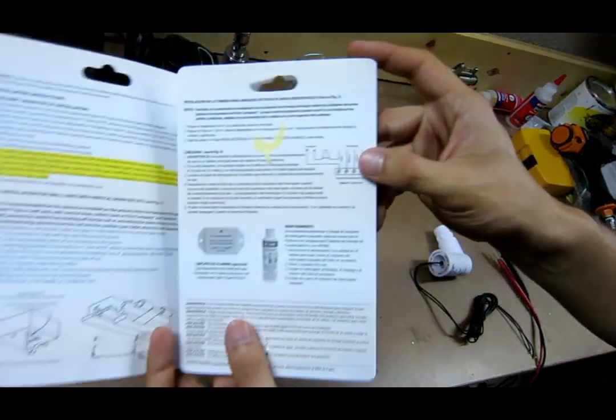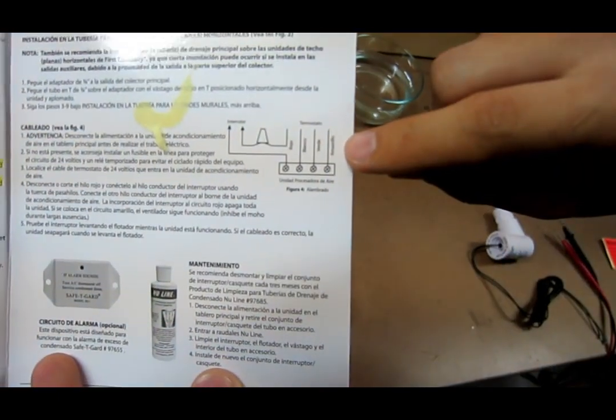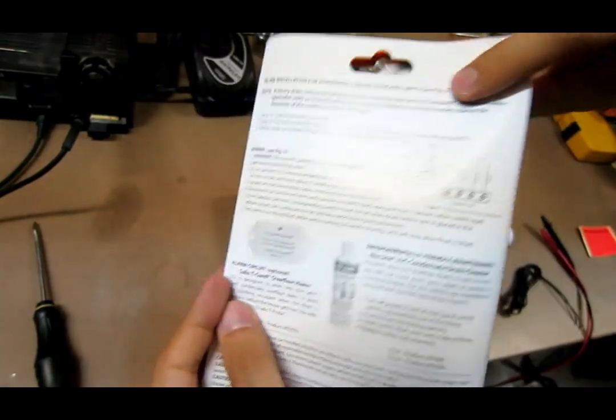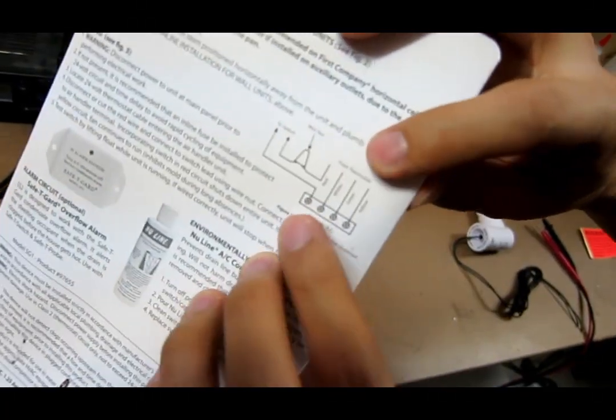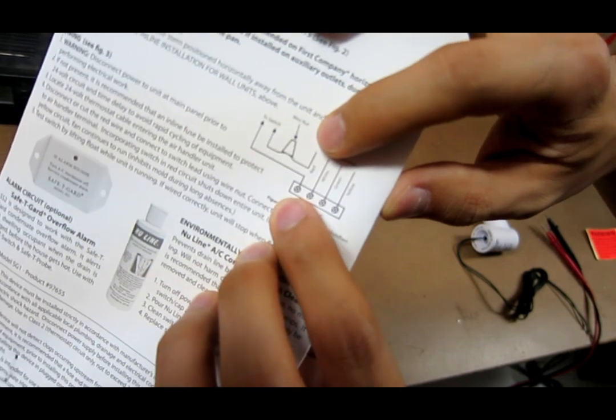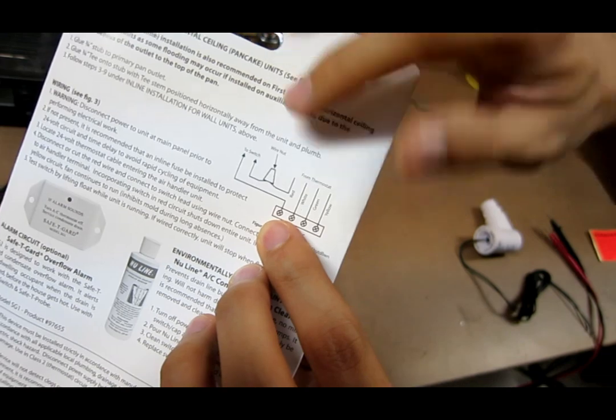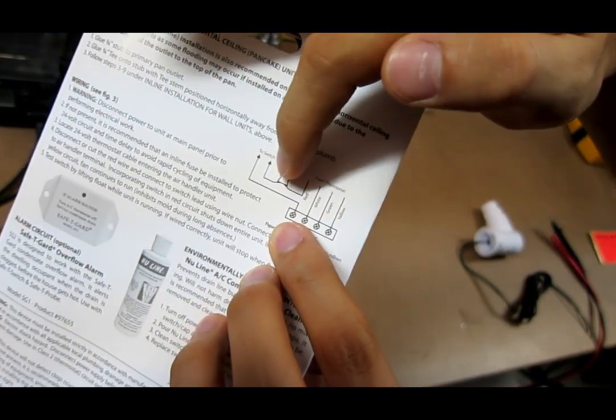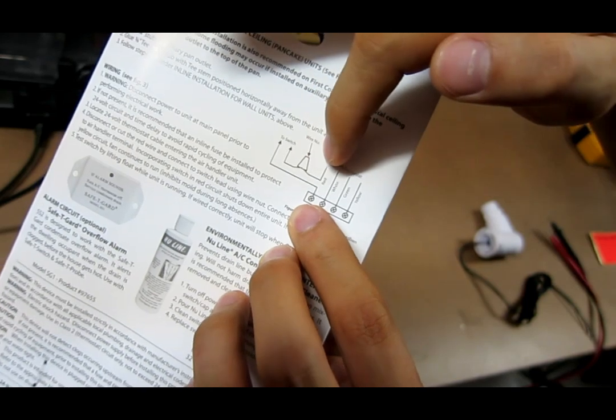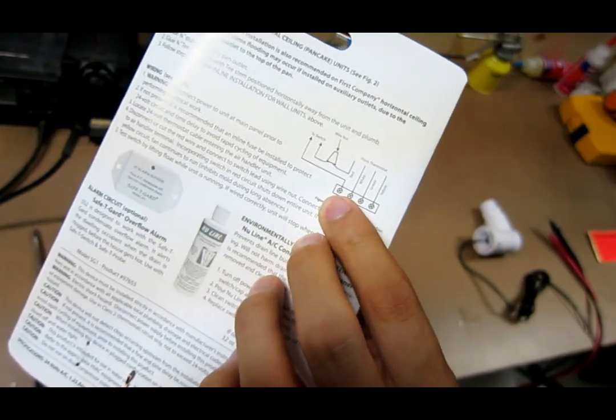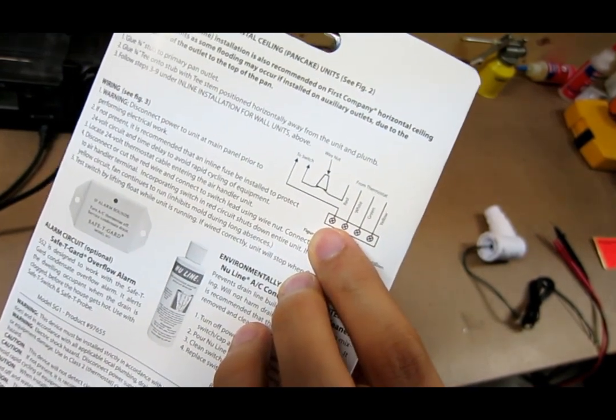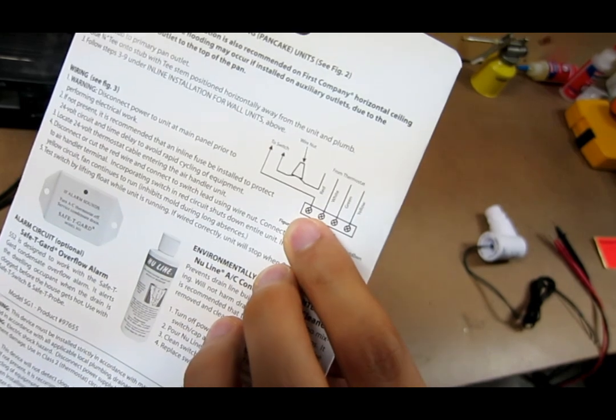So this device right here attaches to the 24 volt AC supply voltage. It's in between the return of it, so it acts like a switch. If there's too much water that condenses and builds up a flow of water, then it shuts off.